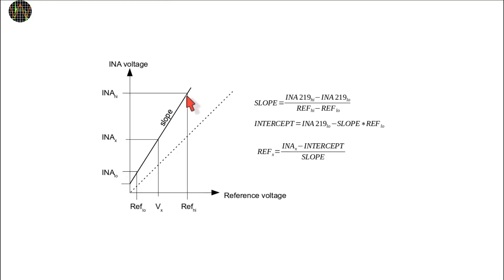Using these four values you can then calculate a slope and an intercept value which become the calibration data. With these two values and that formula here, you can then correct the measured INAx value to become refx.